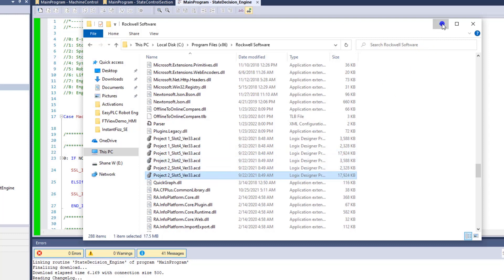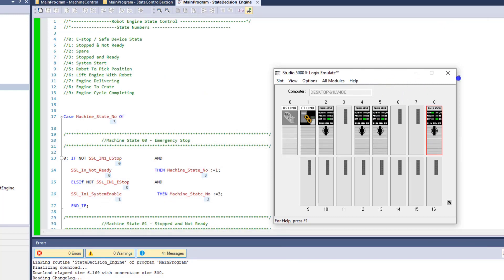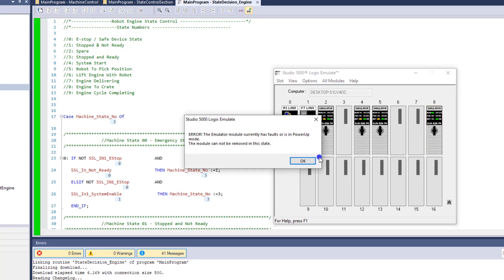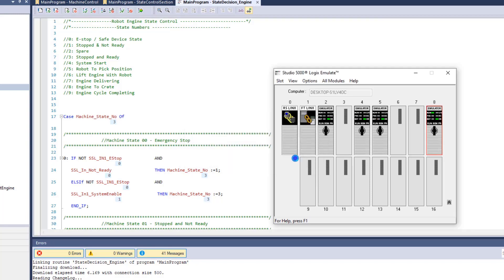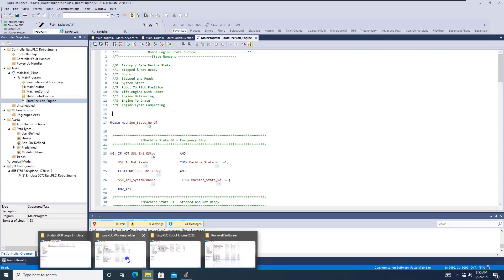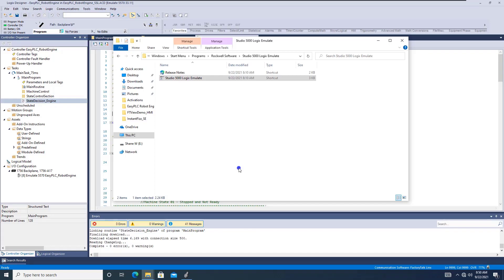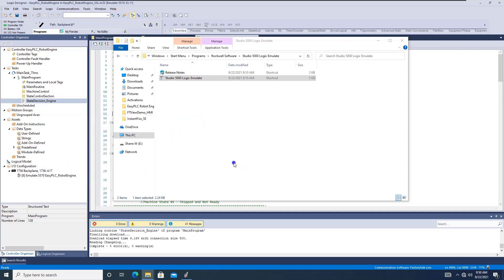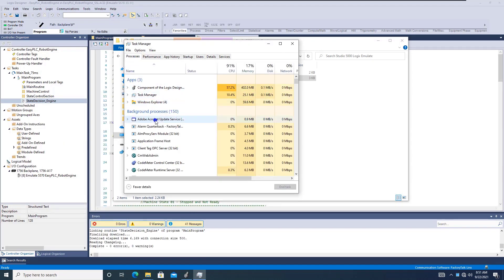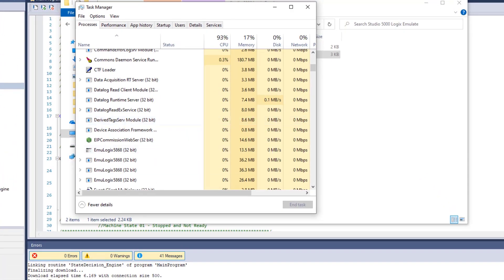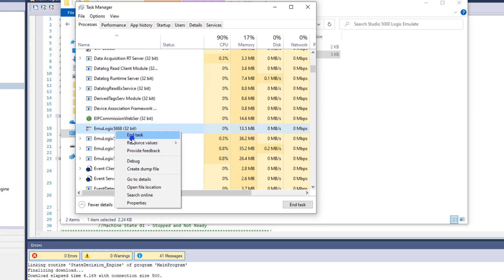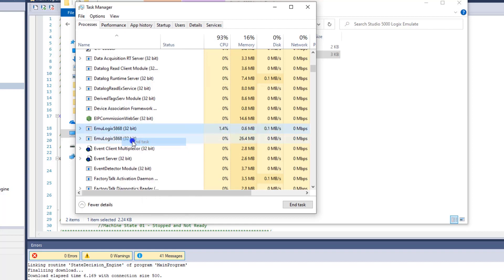Another key thing: if you shut Studio down and get an error, here's a helpful tip. Crank up the emulator — now 90% of the time it's going to fail at this point. There's no reason to stress; I'm causing this problem on purpose to show you how to recover. It thinks Emulate is open but it's really not. Go into Task Manager, go to the Processes tab, verify the emulator is not open on your taskbar, then right-click each process and End Task on all your Emulate Logix Processors.